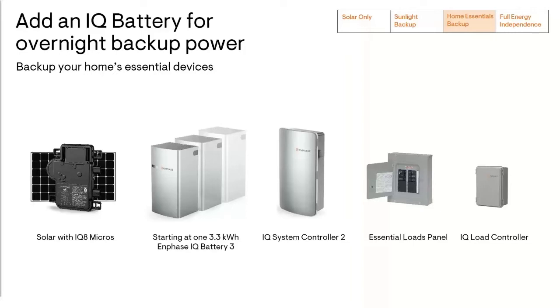An essential loads panel and IQ load controller are highly recommended to limit the number of loads backed up by a relatively small battery, and again, to shed large loads which could potentially overload the battery or drain it quickly.